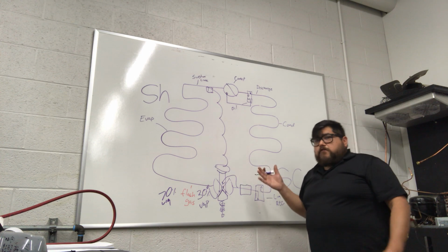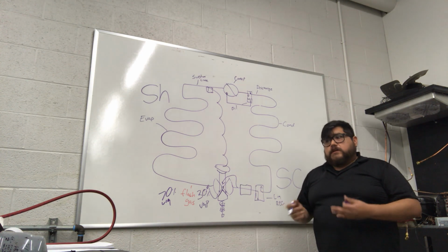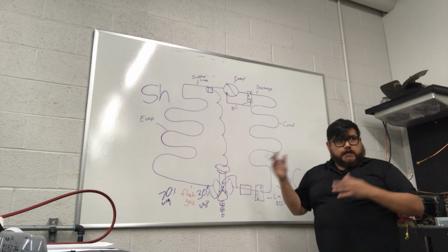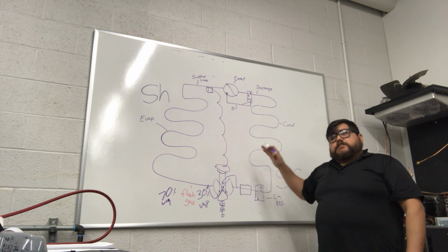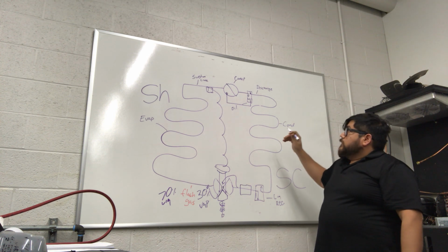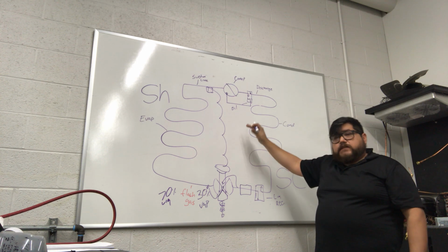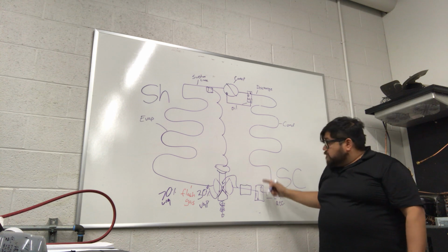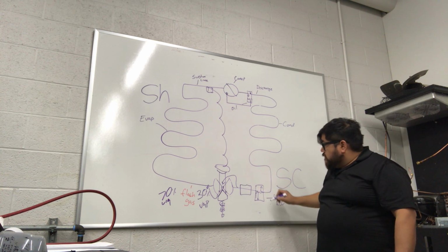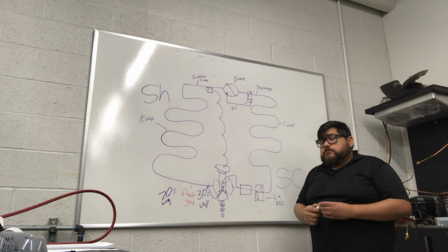inside of our unit. Now, why would we need to store refrigerant? Normally, we size these units for a specific load, this temperature range, and so on. In refrigeration, which is a little different from air conditioning, sometimes we can overfill this unit for its worst case scenario. And then once your load gets down to temperature, we have an excess of liquid. What do we do with that liquid? We store it so we don't flood our compressor, damaging our compressor.